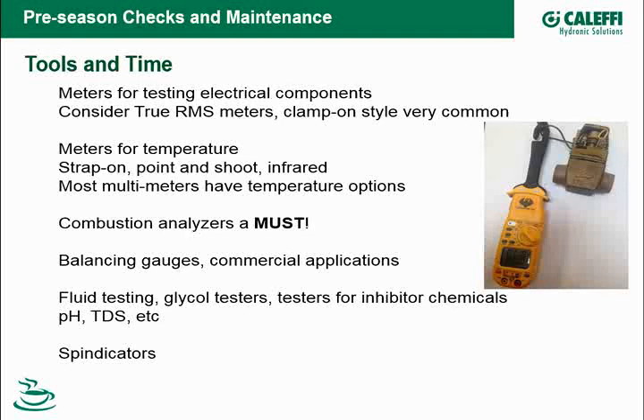Fluid testing. In the last couple months, I've been doing a lot of traveling. I was back east all last week, and there's a lot of concern about fluid testing. I think the time has come that with these little high-efficiency boilers with small tube heat exchangers, if there's issues out there with those overheating or starting to fail or starting to get pinholes, most of the time it's going to be related to the fluid that's going through them, whether it's just water or if it's glycol.